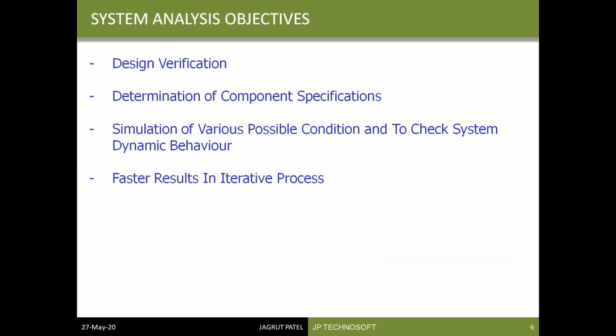While designing the system, we have got another objective that is called power system analysis. When we are talking on electrical power system network, we have got analysis tools also. So what is the purpose of analyzing a design to be implemented? So basically the first objective is to have design verification. Suppose we have designed a transformer rating, then we should have confirmation on its rating. So by performing analysis tools, we can check whether the size which we have decided is proper or not. Then determination of component specification, the voltage rating in case of a transformer is taken proper or not. This should be again a second objective.